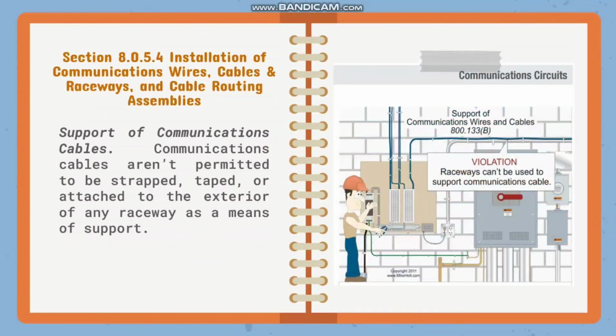So next naman po is section 8.0.5.4, installation of communications wires, cables, and raceways and cable routing assemblies. Support of communications cables. Communications cables aren't permitted to be strapped, taped, or attached to the exterior of any raceway as a means of support. So yung nasa illustration po is a clear violation sa section po since yung raceway ay ginawang means of support para sa communication cable.